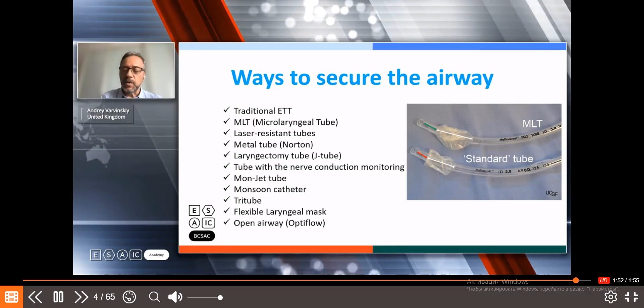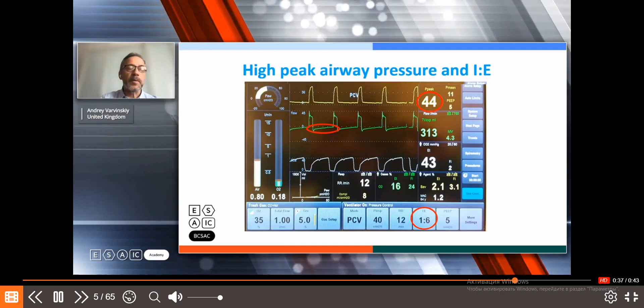Okay, and then indeed there's the open airway, no tubes at all, using something called Optiflow, a high flow humidified oxygen. You need to be aware that the smaller the tube, the higher the peak airway pressure will be. And on this particular screen, you can see that the peak airway pressure in this patient's airway is up to 44, delivering a tidal volume of only 300 mils. But you can see at the bottom the I:E ratio is 1:6, so you need a lot of pressure, sometimes, particularly in a partially obstructed or narrowed airway, to deliver your tidal volume.